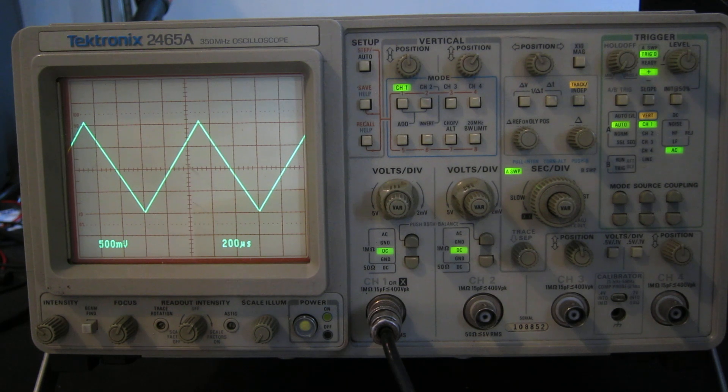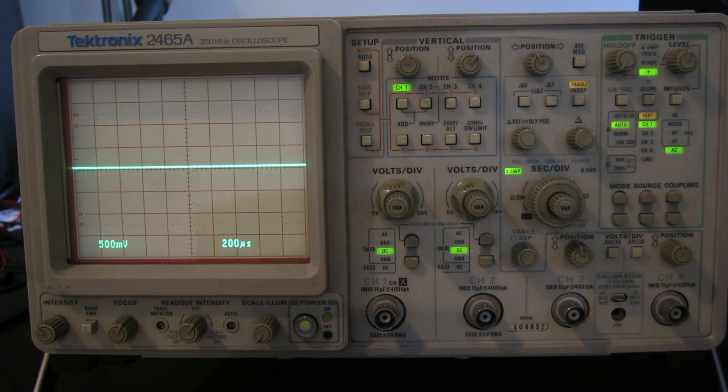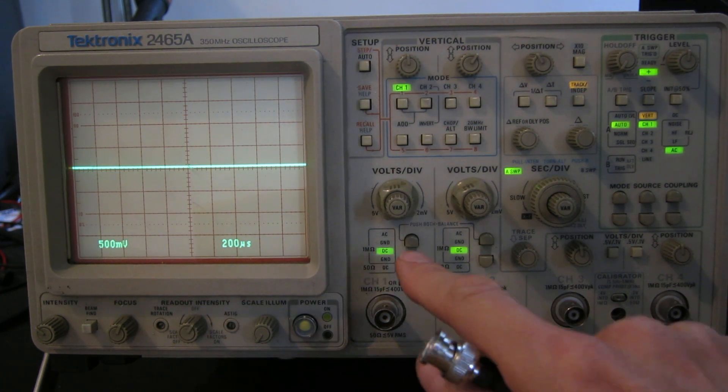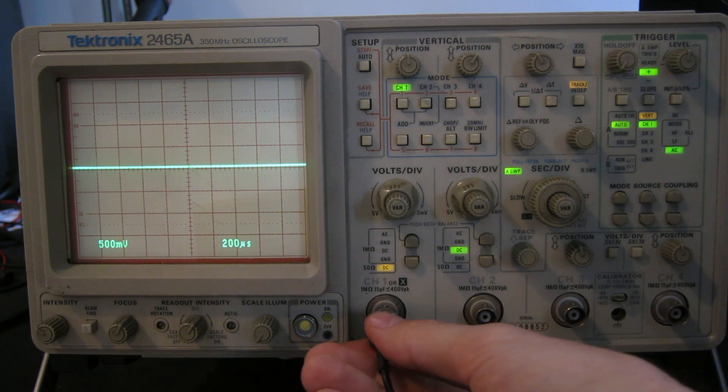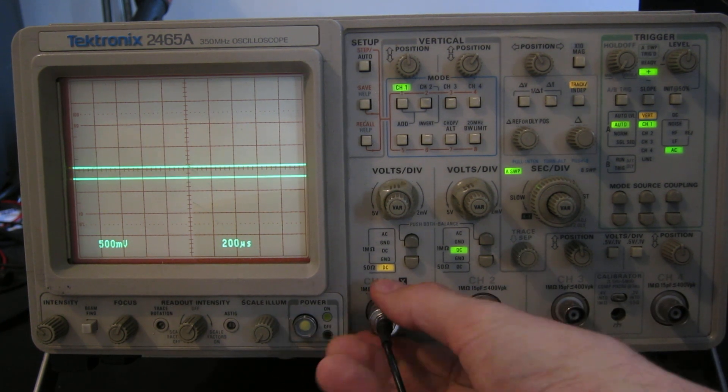We'll check the scope's bandwidth. It's rated 350 megahertz. To do that, we need a fast rise time pulse, which I have on this signal generator here. We need to put the input onto a 50 ohms terminated mode to get maximum bandwidth and accuracy. Turn up the sensitivity. Intensity a bit.